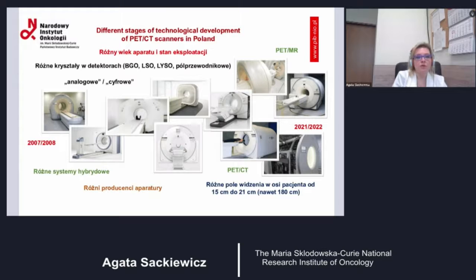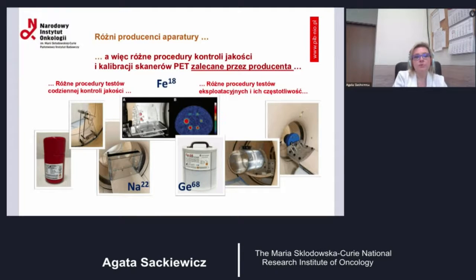We need to remember that there are numerous aspects concerning manufacturers themselves. So, depending on the manufacturers, there are different recommendations on how to conduct quality control and calibration procedures. So, there are scanners that have to be covered by daily routine quality tests. There are different performance tests for which sodium-22 isotope is used, so different phantoms are used. They are filled with germanium. We need to remember that depending on the manufacturers, we will be using phantoms that will contain the sources for calibration of this equipment.